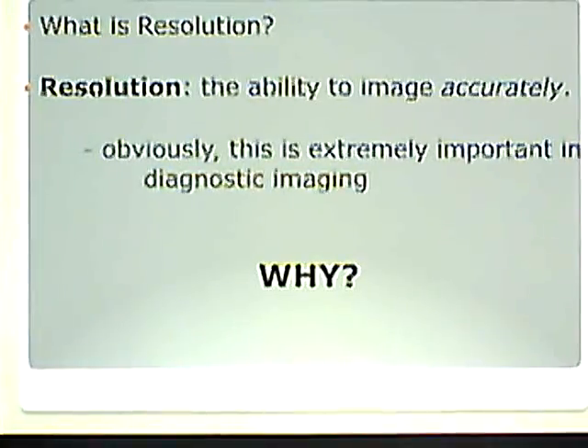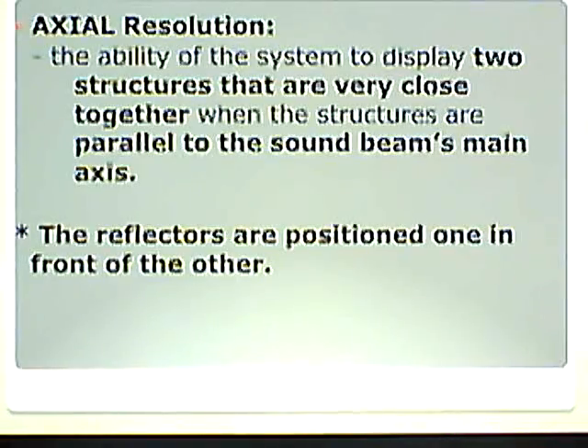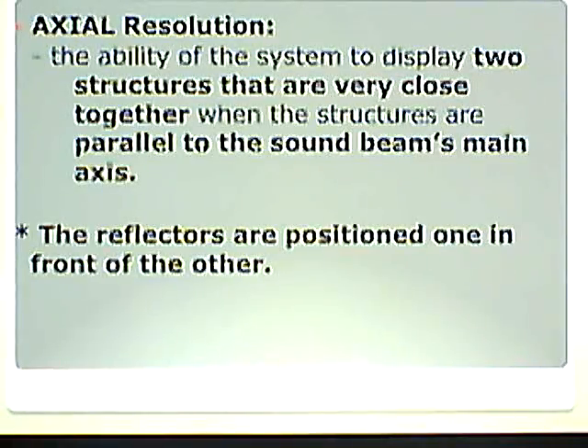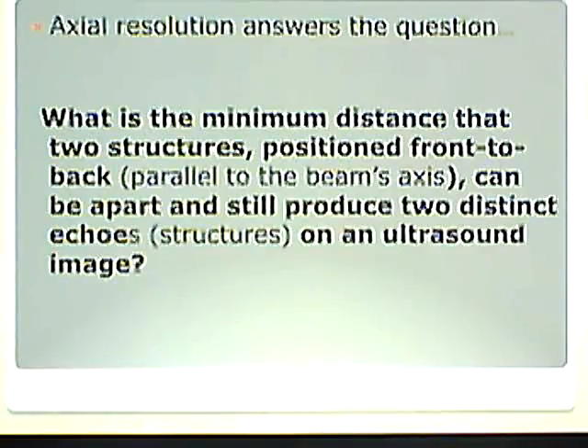Axial resolution is the ability of the system to display two structures that are very close together when those structures are parallel to the sound beam's main axis — meaning they are front to back. They're not straddling the line or going across it — that would be perpendicular. Just like looking from the front of a room to the back, the reflectors are positioned one in front of the other. Axial resolution answers: what is the minimum distance to still see two structures as distinct?